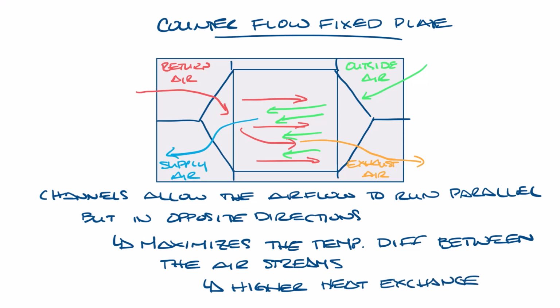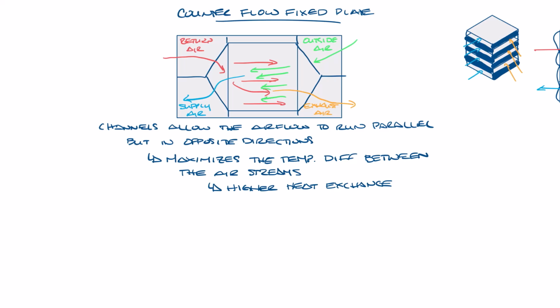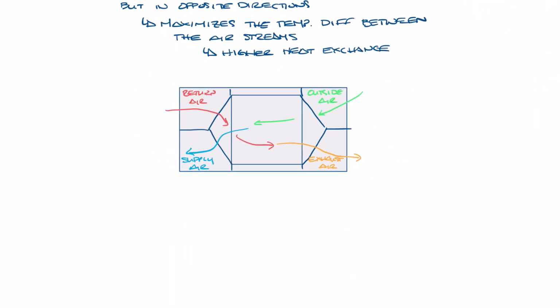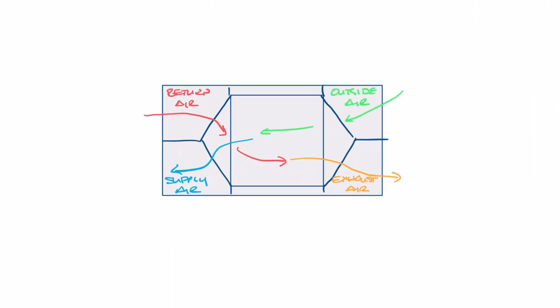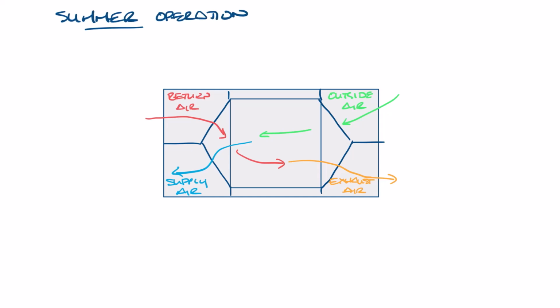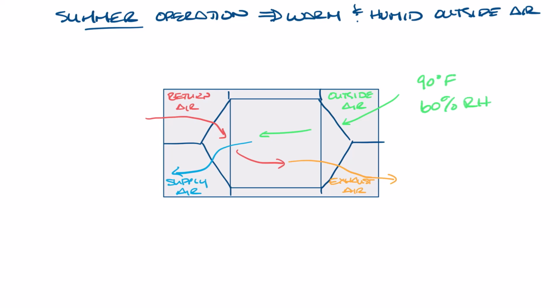So now let's look at the way the air moves through the ERV. The concept is again the same for ERVs and HRVs and for wheel and fixed plate units. So let's just work with this drawing, and I'm going to make a copy of it and move it over here somewhere. In the summer, you have warm and, depending on where you are in the country, possibly humid outside air. So let's call it 90 degrees and 60% relative humidity. It comes into the unit and passes over the wheel or through the plates.